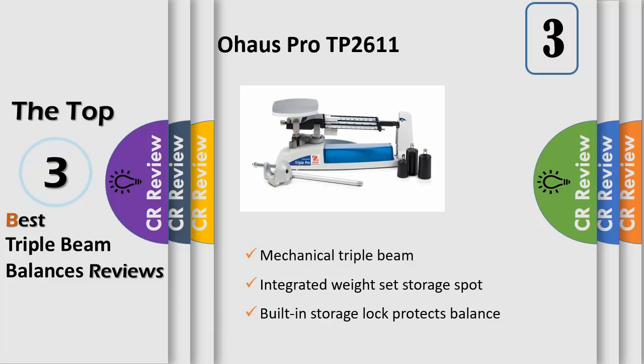500 grams, and 100 grams sliding weights, also called riders or poises, along the 3-notched tiered beams. It has a spring-loaded tare adjustment to prevent accidental changes to the setting and obtain precise results, and a rod and clamp assembly for below-balance weighing to determine specific gravity.